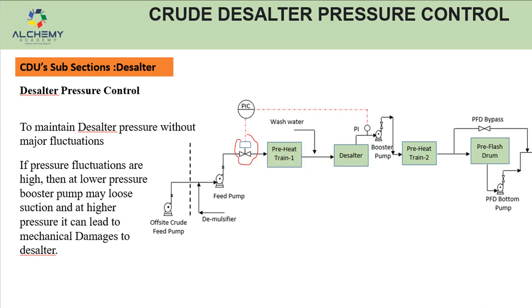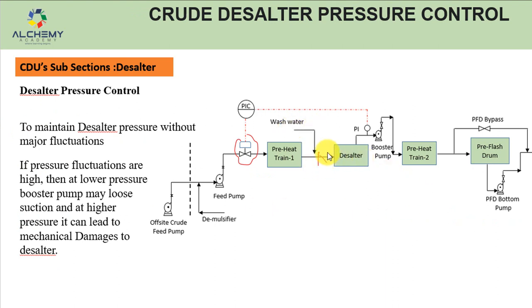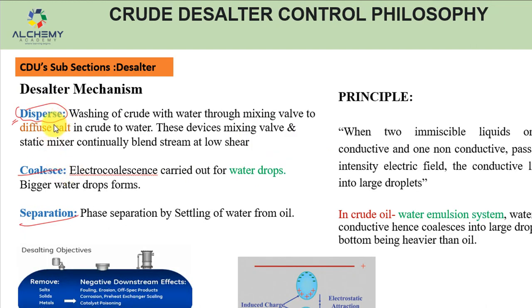After the preheat train, crude goes to the desalter where removal of impurities, salt and water happens. The first mechanism is disperse — washing of crude with water through a mixing valve to diffuse salt from the crude into the water. Wash water is injected and when the mixture passes through the mixing valve, the water and crude are thoroughly mixed. Whatever trapped or dissolved salt is present in the crude gets dissolved into the water before it enters the desalter.